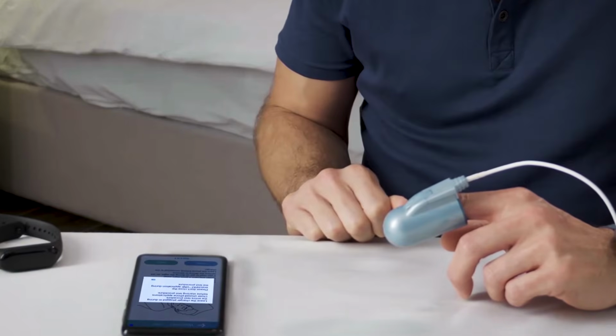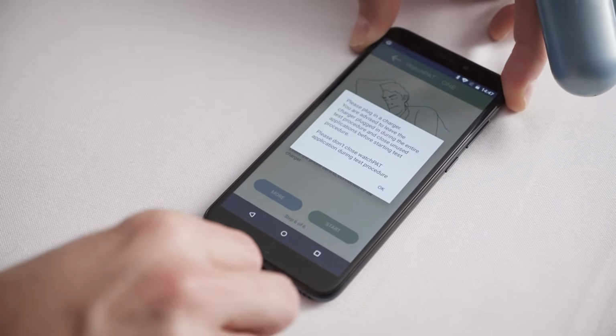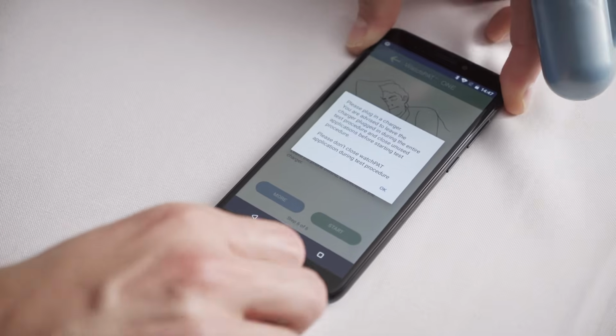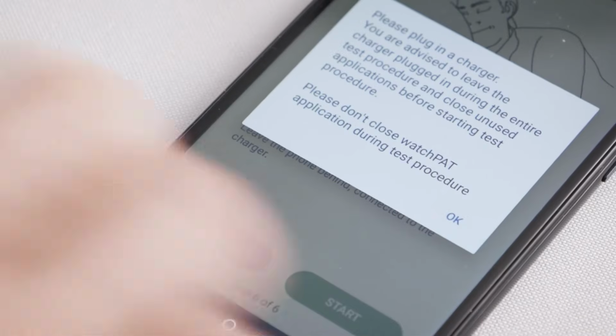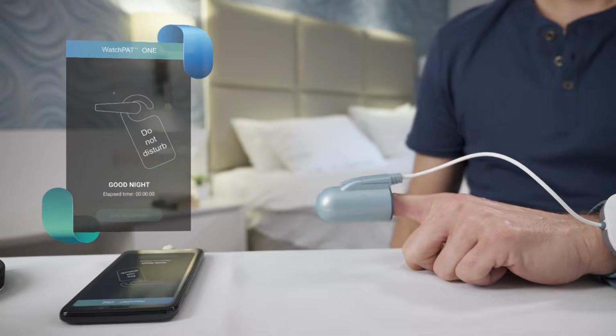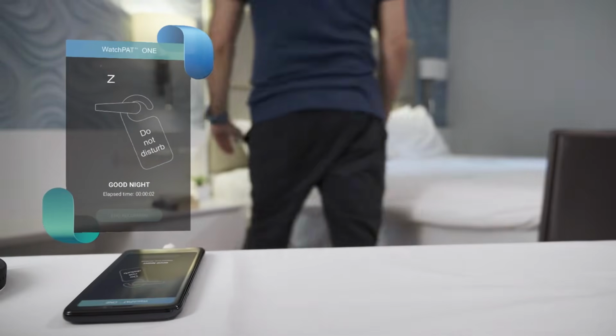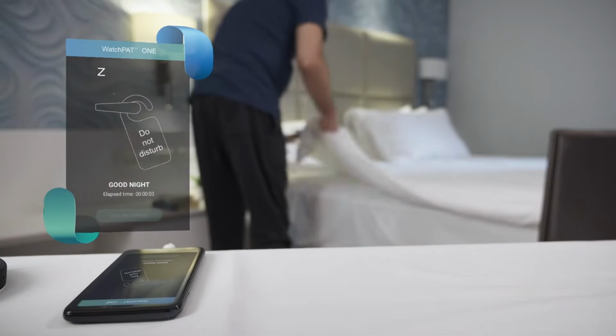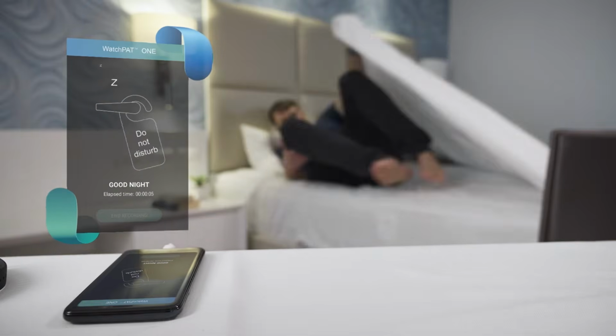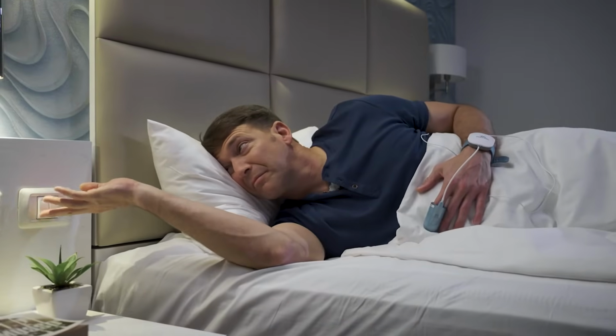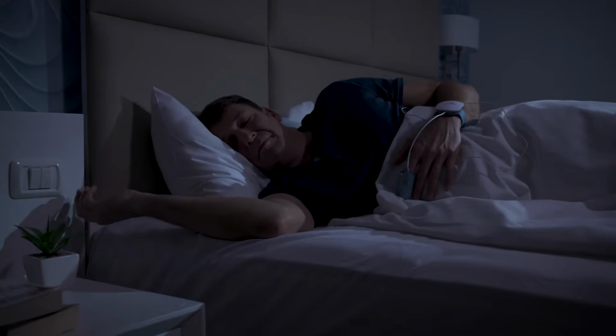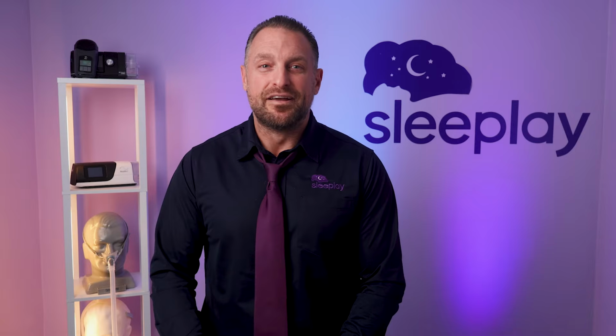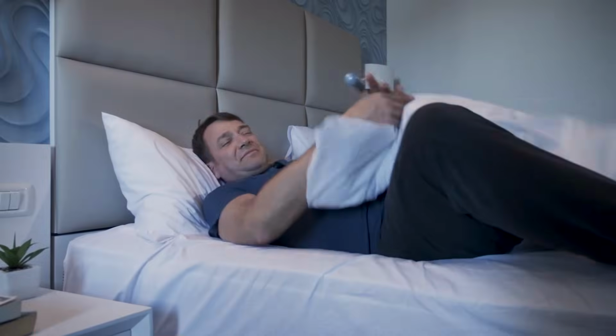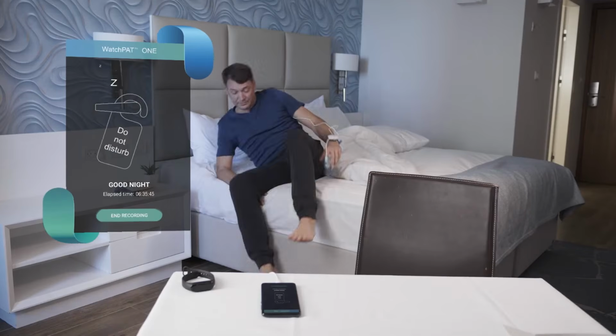You should be fine placing on your nightstand or dresser next to the bed. Make sure to turn off all other transmitting devices in the room that may interfere. Simply press start when you're ready to go to bed to start your test. Keep the phone plugged into the electrical outlet all night. If you need to go to the bathroom, just go, and when back, the WatchPAT device will automatically reconnect to your phone if needed. Once up in the morning, simply press end recording on the app.